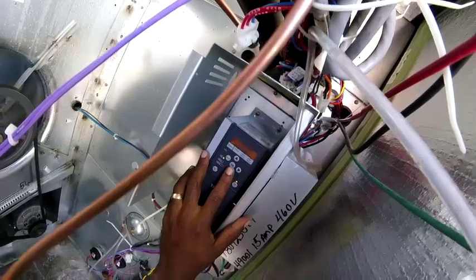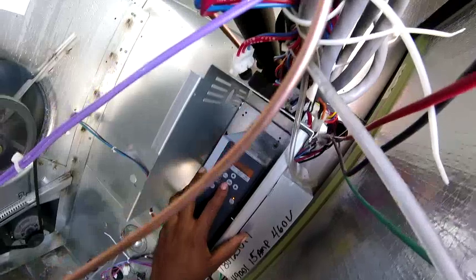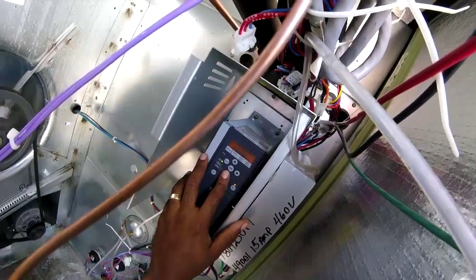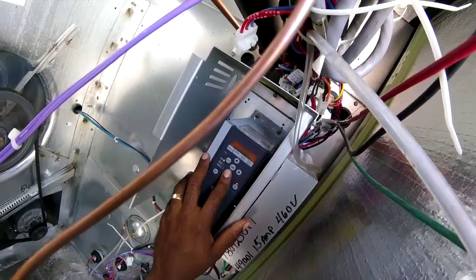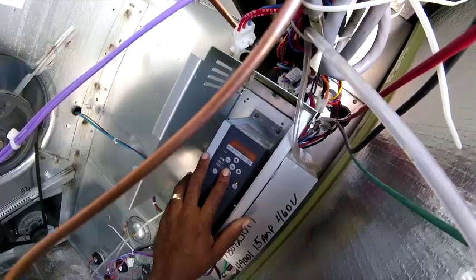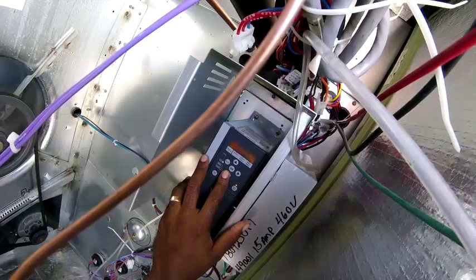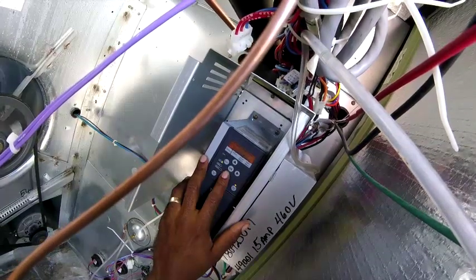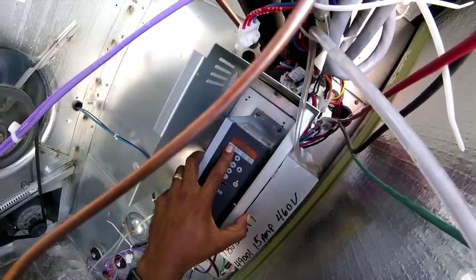1 to 23, what's that motor frequency? It says 60 hertz. Yeah, everything is already entered in. My motor speed low is at 30 hertz. My motor speed high is at 100 hertz. So I guess it's just calling for 50 hertz.